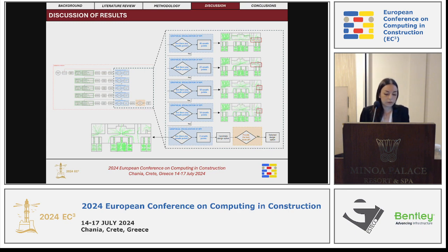Overall, in this first fire scenario, where the fire was located along the main escape route, five design options were evaluated. In the first four design options, there is at least one location where the KPI exceeds the threshold. The last option, where all points are safe for occupants, is labeled as the candidate design option.